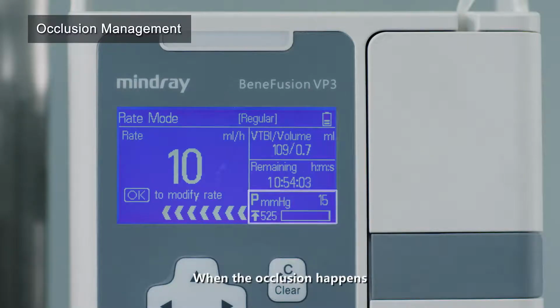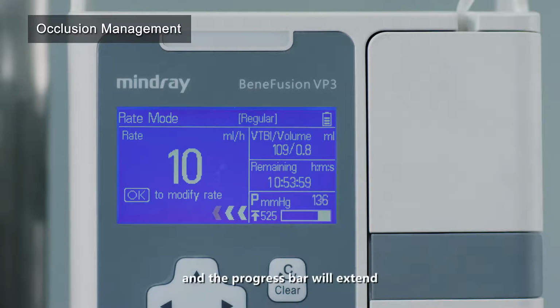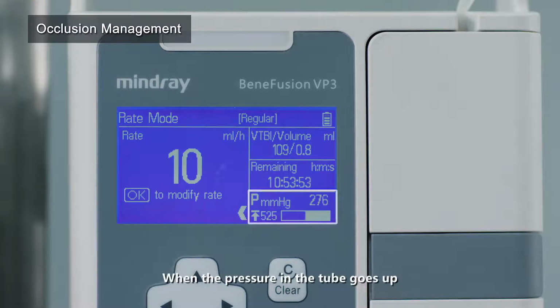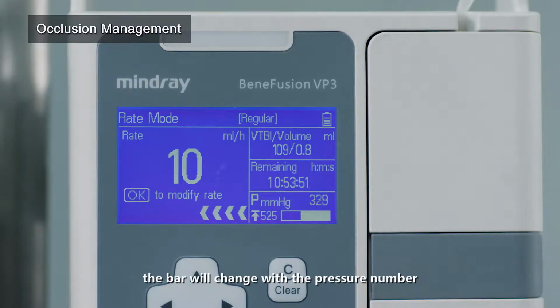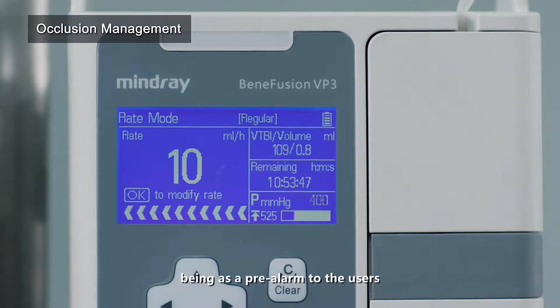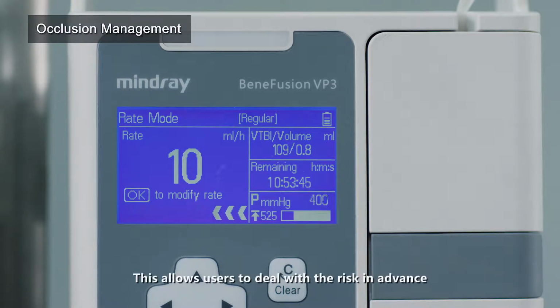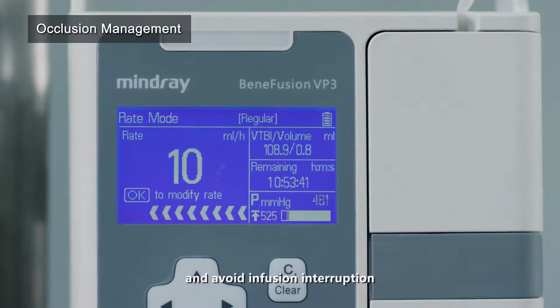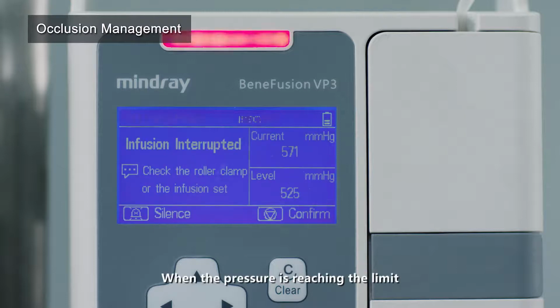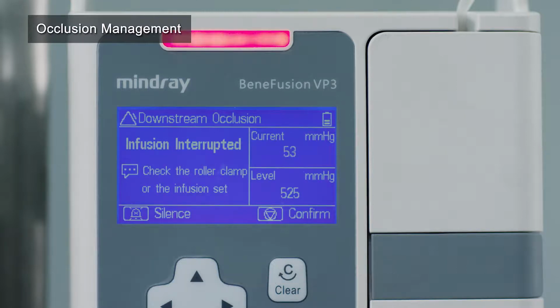When the occlusion happens, the pressure number will increase and the progress bar will extend with the real pressure in the tube. When the pressure in the tube goes up, the bar will change with the pressure number, acting as a pre-alarm to the users. This allows users to deal with the risk in advance and avoid infusion interruption. When the pressure is reaching the limit, the alarm will be triggered.